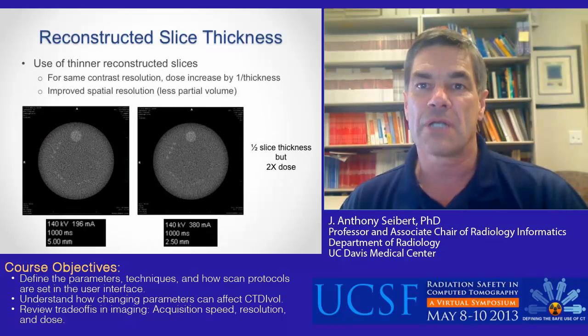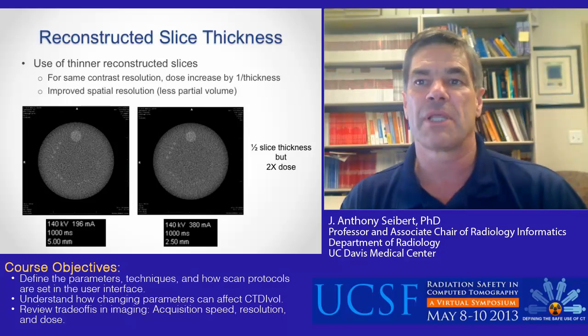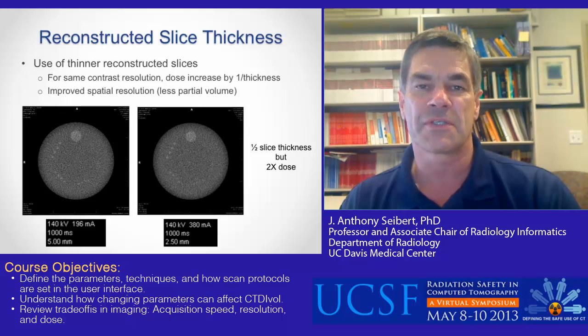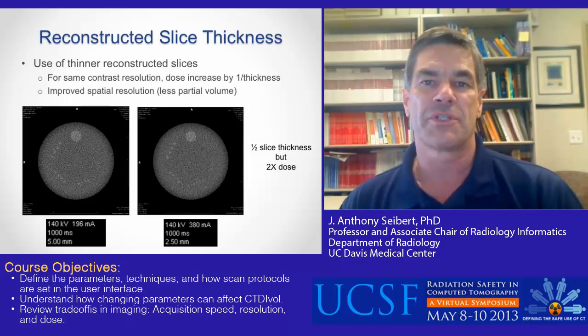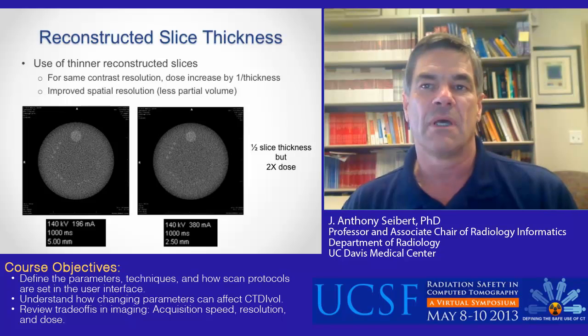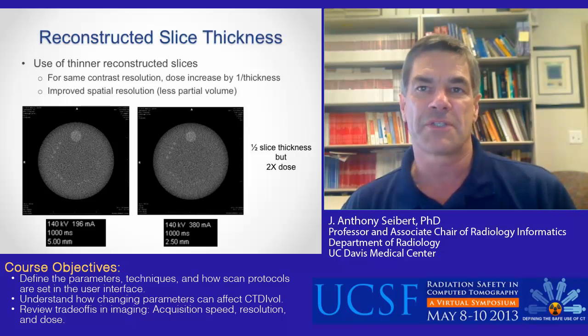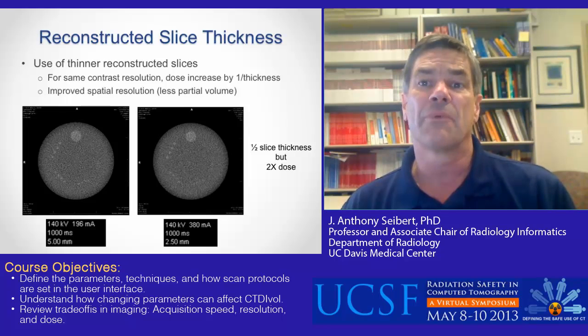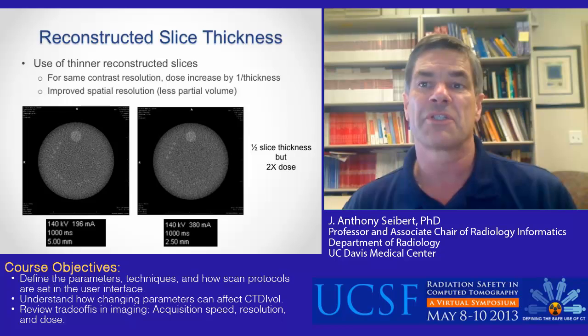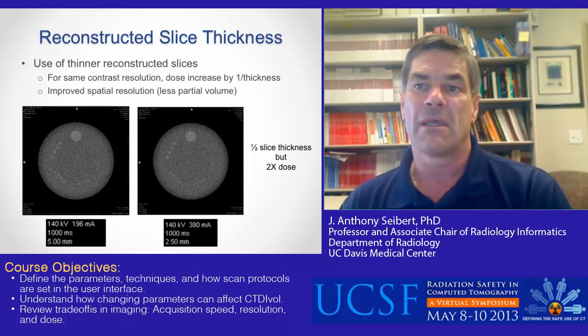A low contrast phantom demonstrates the relationship of the impact of using thinner slices while keeping the contrast-to-noise equal. On the left is a scan with 5 mm slice thickness using 196 MA. On the right is a scan with 2.5 mm slice thickness using 380 mA, with twice the dose.